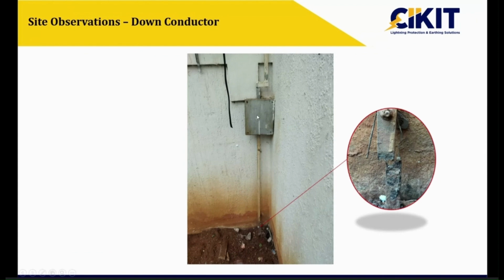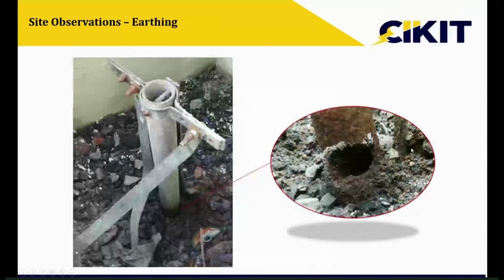Here you can observe that the strips look fine above the soil, but they were completely corroded when we removed the first layer of the soil. Here you can see that the pipe is very good from outside, but when we remove the top layer of the soil, there is no connection to the remaining part. From both the images, you can observe that the rate of corrosion is much higher at the point where the pipe is entering into the soil. At that particular portion the rate of corrosion will be more.